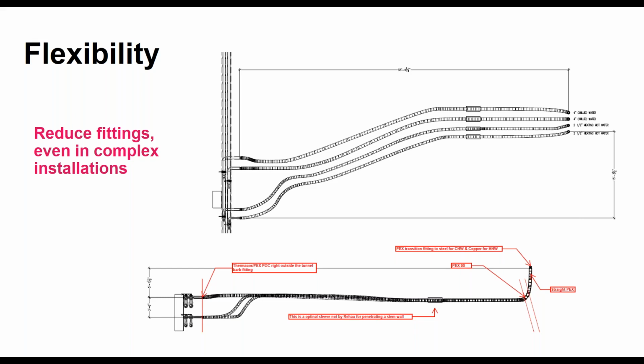It's 4-inch pipe—two 4-inch runs on top for the chilled water, and two 2.5-inch runs on the bottom for the heating hot water. The contractor in this case wanted to run flexible pipe midway through. You can see where they have those bump-outs—that's a potential inline coupling. They were trying to figure out how to negotiate penetrating a stem wall.